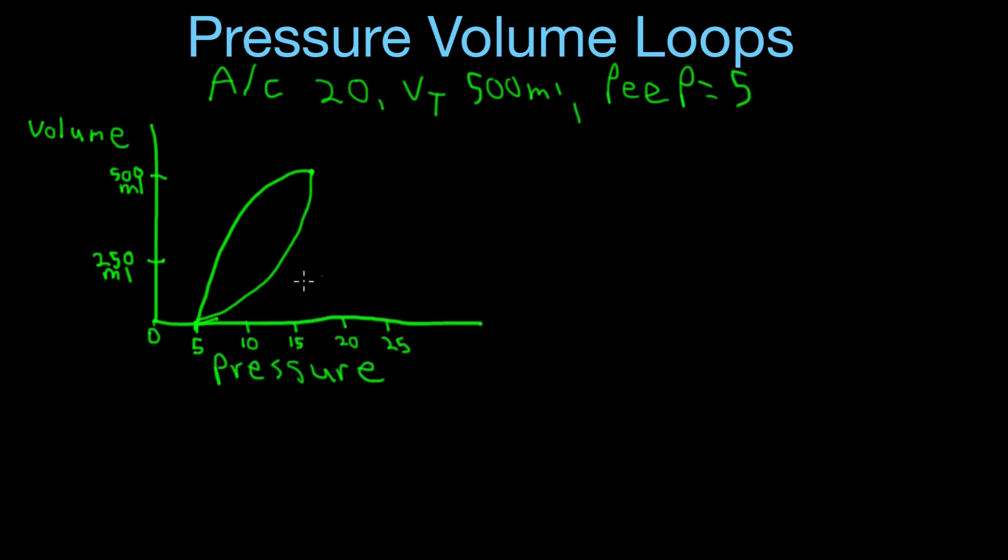And so if we had the PEEP set at let's say 10, then it would start right here on that breath and it would just go up in the same manner on inspiration until it reached that target tidal volume, then it would start to go back down to the set PEEP level.